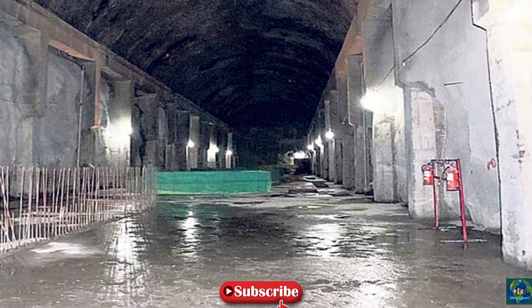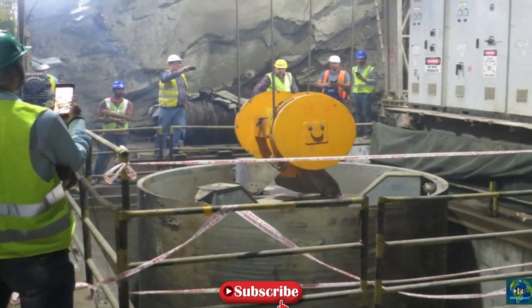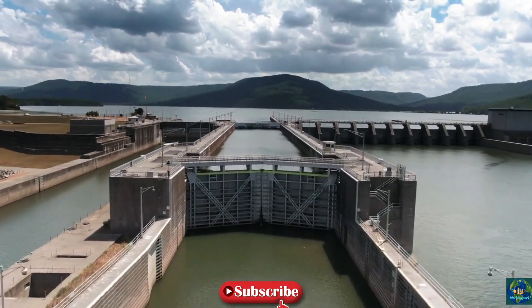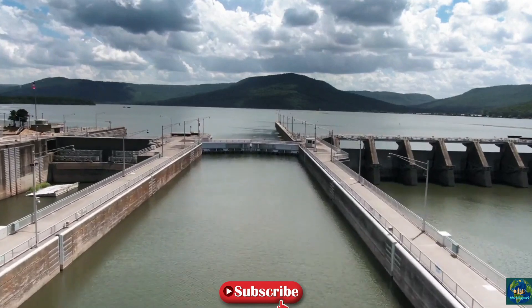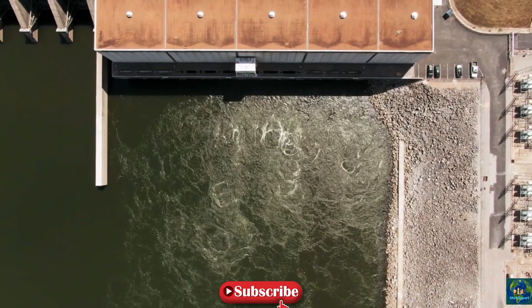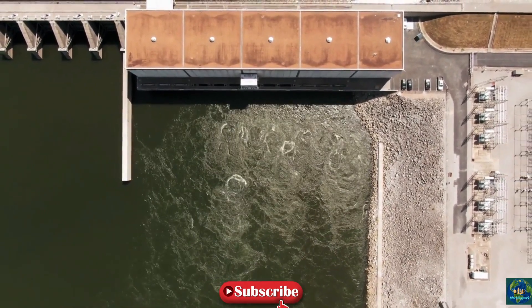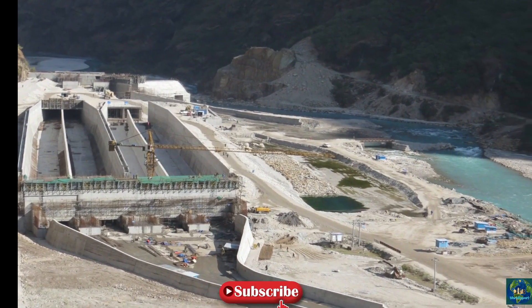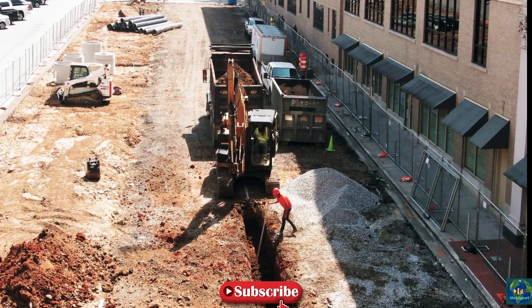The company has planned to develop hydropower projects in the Tamakoshi River Basin. Upper Tamakoshi comprises a 22-metre high and 60-metre long concrete dam, two 225-metre long desanding basins, and an 8.4-kilometre long headrace tunnel with a 32.14 square metre cross-sectional area, and an underground powerhouse 142 metres long, 13 metres wide and 25 metres high, equipped with six Pelton turbine units. The power generated will be fed into the national grid through a 49-kilometre long double-circuit 220-kilovolt transmission line between Gongar and the Khimti Power Station.